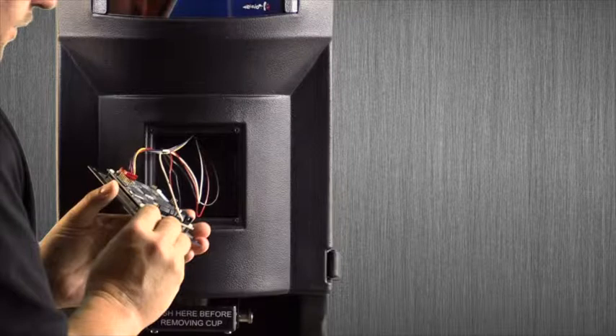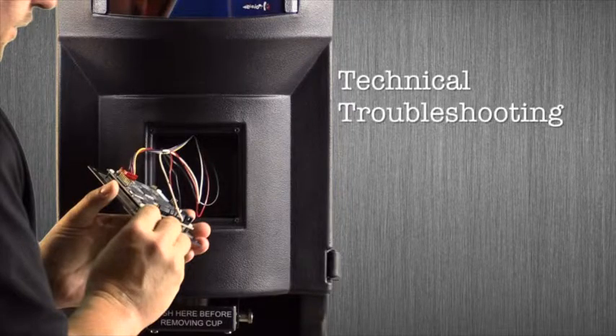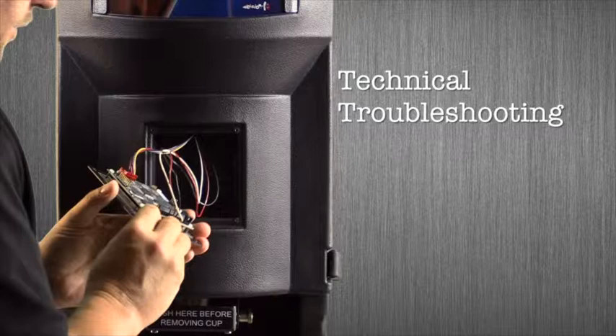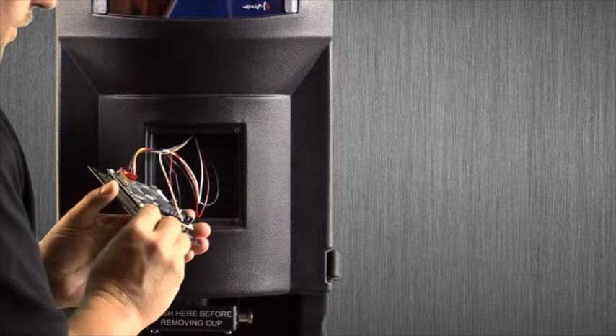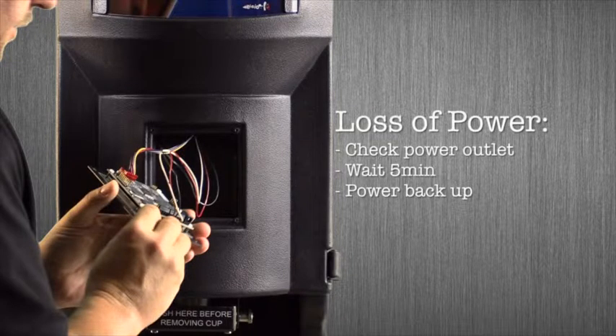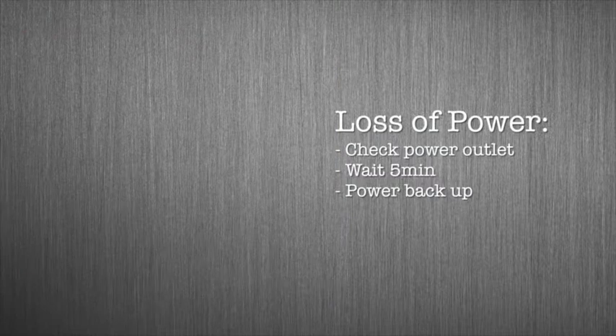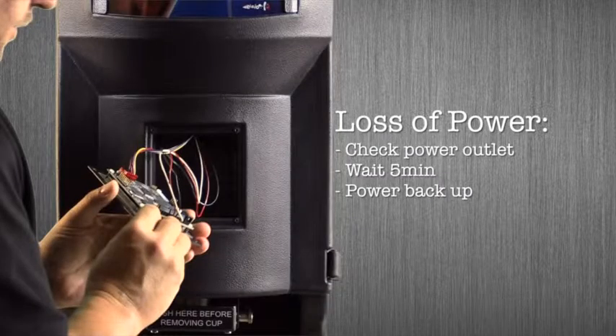The next section of our training will include technical troubleshooting. At this time, we'll be discussing the basic verification and repair of certain unit failures that can be resolved at the store level. Loss of power. We need to verify that the unit is plugged into a dedicated outlet. If this unit is not showing anything on the main screen and/or is blank, the unit will need to be powered down and unplugged from the wall outlet for no less than 5 minutes, and then powered back up.